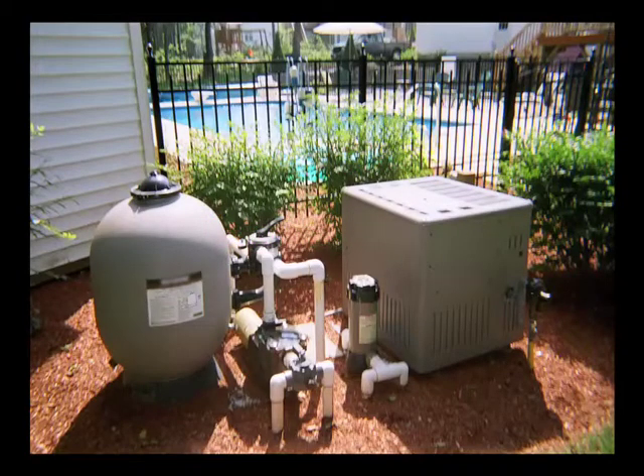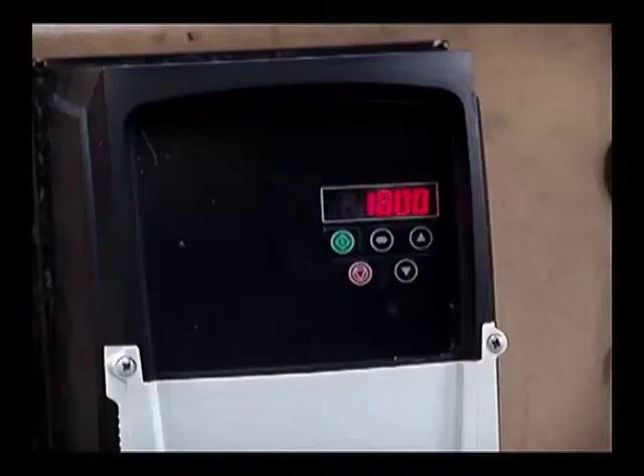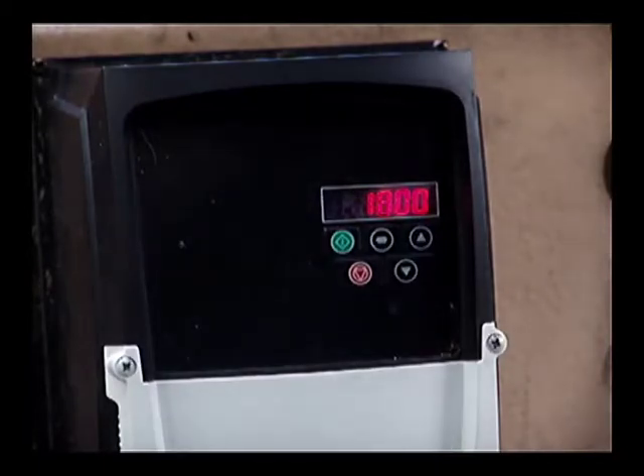The key benefit besides the power saving is that the pool filters are set for a maximum and minimum flow rate. Now at 3000 RPM, it is way too much power for the filter itself. And by dropping it down, it will make your filter work better. So your pump is happy because it's running slower and quieter and cooler. Your filter is happy because it's running inside its guidelines, and further, your pipe work is under less pressure.